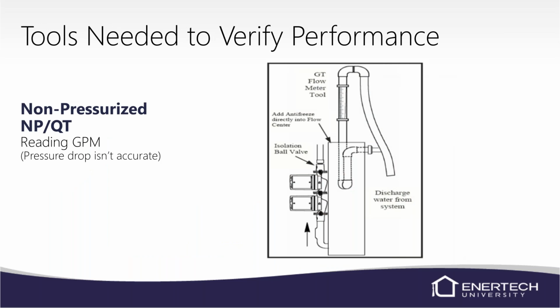On a non-pressurized flow center, you can put in a flow meter tool. We have a 1 through 10 and a 1 through 17 GPM flow meter tool that you can put into the tank and leave it, kind of like a sight glass on a boiler. I would not recommend that, only because water is nasty.